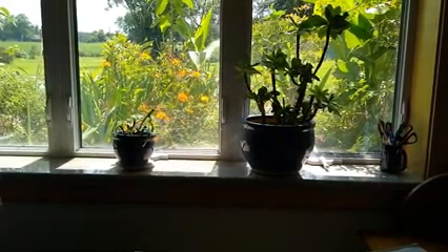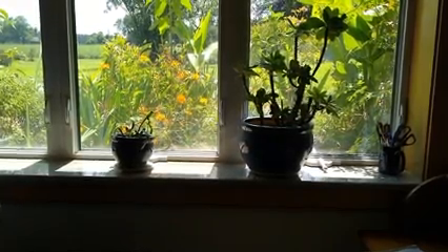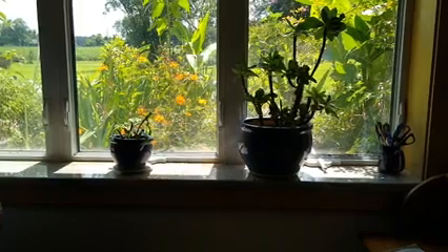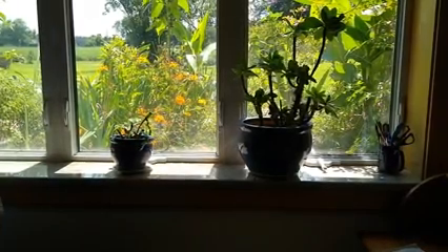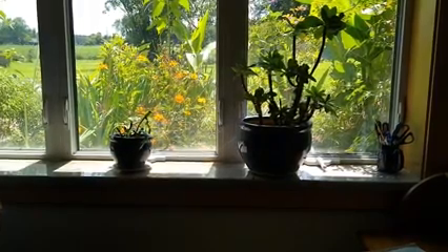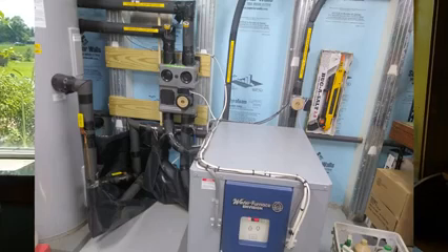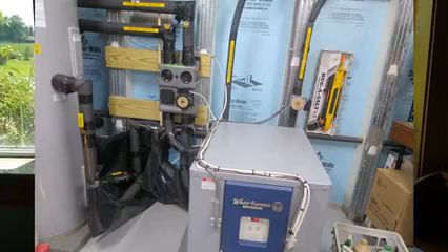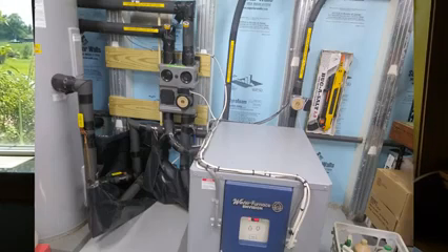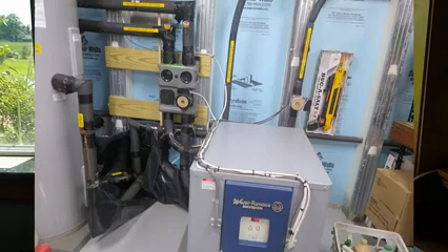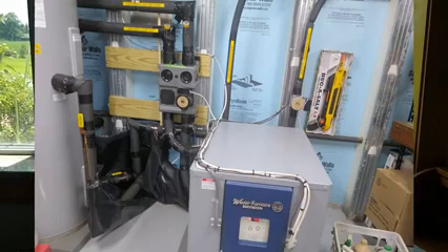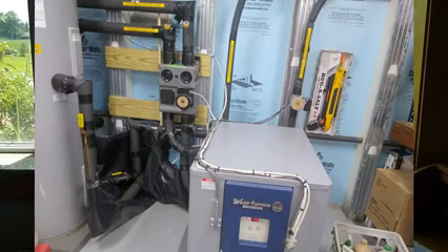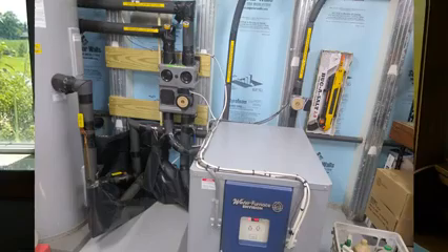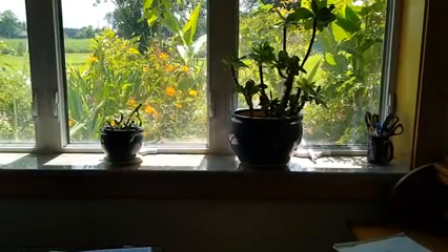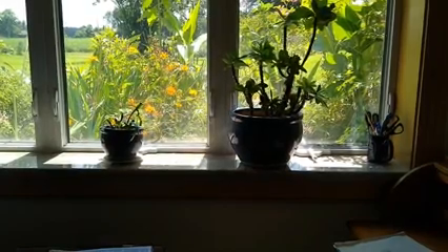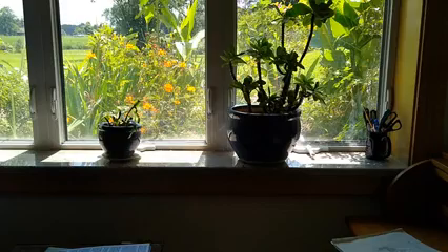The energy demand of appliances is of course part of the picture, and an electric stove, electric clothes dryer, and electric water heater all contribute to the total energy demand. The house is heated and cooled by a geothermal heating and cooling system, more correctly described as a ground source heat pump system. My calculations suggested a heating and cooling load of 1 ton, or 12,000 BTU per hour. The availability of suitable high-efficiency equipment led to the installation of a 3-ton WaterFurnace geothermal heat pump, water to water, with 3 200-foot wells in the ground loop. It runs about 1/3 of the time in coldest weather.